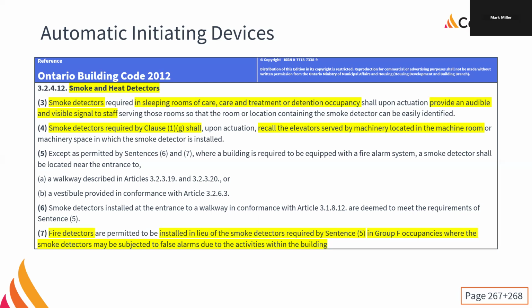And if we have fire alarm systems in a building, and if we have walkways or vestibules, in this case we're talking about walkways to other buildings and vestibules that tie us into other buildings. If we can get from one building to another without going outside, this is what they're talking about. We have to put in smoke detectors near that entrance so that if there's smoke coming from the next building over, we want to know about it.